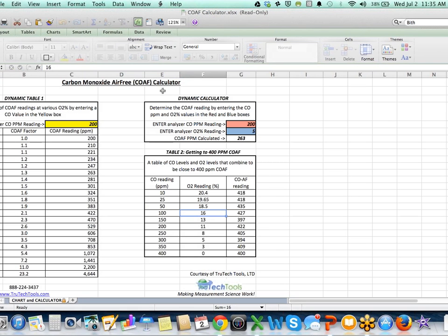And here it is. This is the carbon monoxide air-free calculator. It allows you to do a couple different things to look at CO in different ways, and I've gotten a couple feedbacks. That's the other points which I'm trying to change in here, as well as do the quality control. But if you had a level of CO, say 100 parts per million CO, and you had an oxygen reading available, there's a factor we call developed, that's part of that little equation there, that would lead to a CO air-free reading thusly on the right-hand side. So at 0% oxygen, because it is then CO air-free, it would correspond with 100 parts per million. So that would give you the same raw CO as the CO air-free reading.